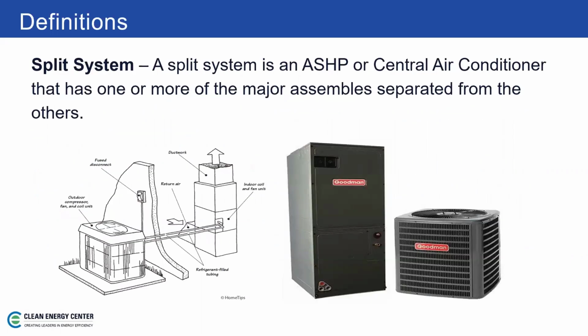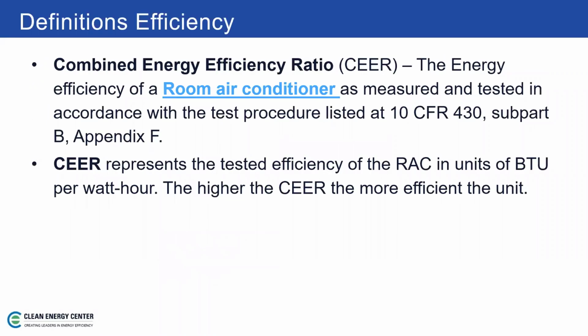And then when we say split system, you hear people say split systems. Basically, we're talking about that conventional system, and it's split because we have an air handler or a furnace or an A coil inside, and it's connected with a line set to the outdoor unit, which in the HVAC world we call the condenser. So an evaporator connected to a condenser via a line set is what we talk about when we talk about split systems. So let's talk about the different efficiencies, because our guidance is that we want to make sure that we install Energy Star rated products when we put them in.